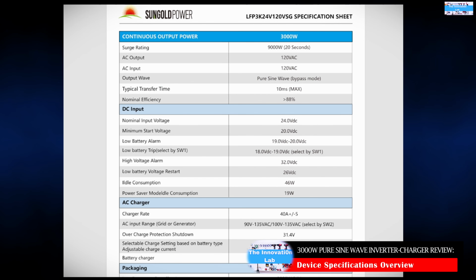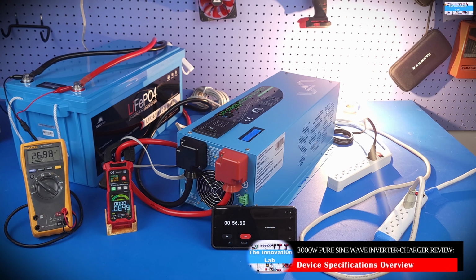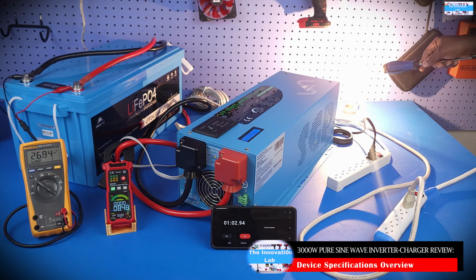It has a maximum transfer time of 10 milliseconds. This means that when transitioning from battery power to AC input power, switching your load from the power inverter to AC, it takes about 10 milliseconds max to make that switch. That's why during the test you'll see a flicker on the light bulb we're using to simulate the load.